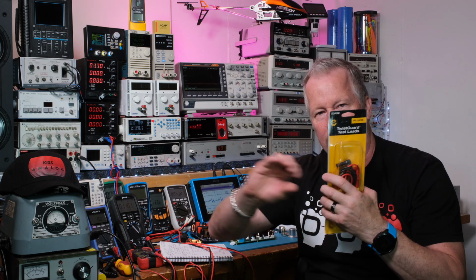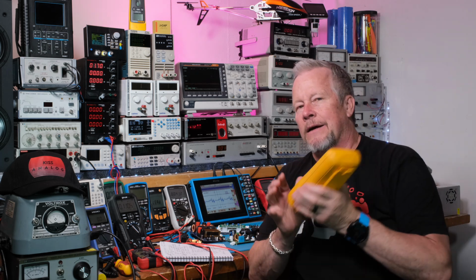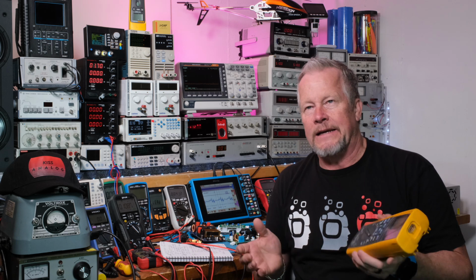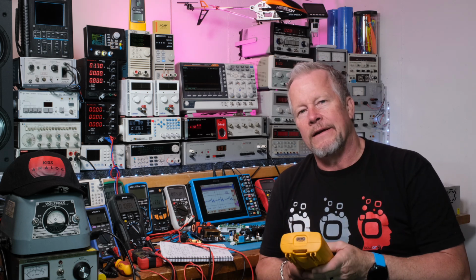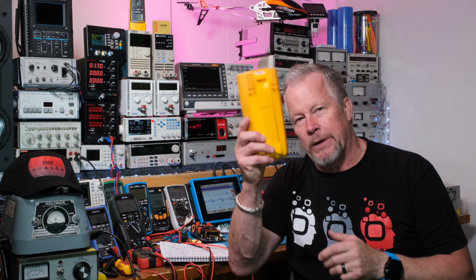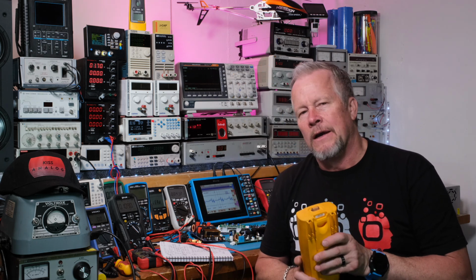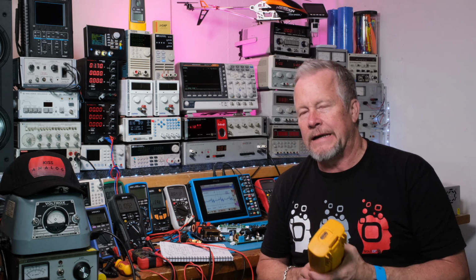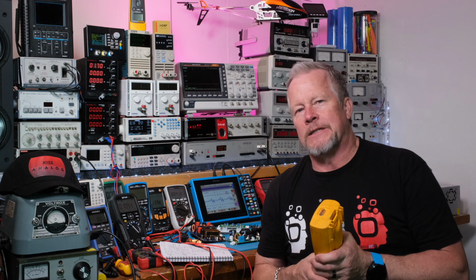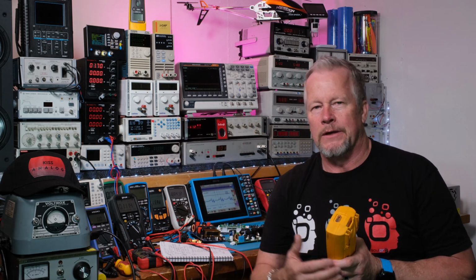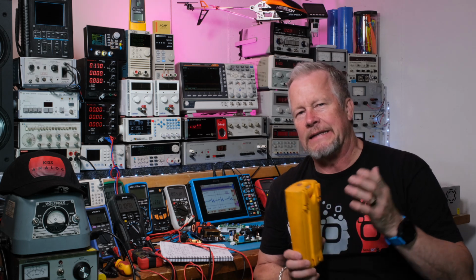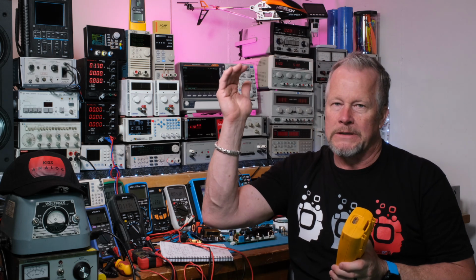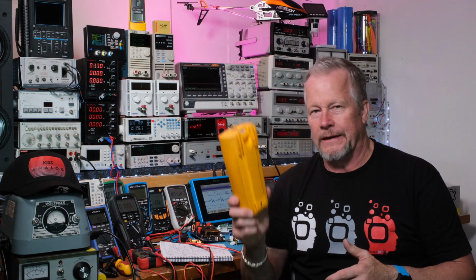These are Fluke's TwistGuard leads, the ones that rotate, and that Cat 4, Cat 3 cover comes down and protects it. By the way, I didn't mention that the Fluke 189, or down here the Fluke 289, and that Keysight meter, they are all Cat 4 meters, right? Cat 4 means the power outside the breaker box, coming to the residence or the building. That dangerous, scary stuff that has a lot of potential energy, more potential for surges and that kind of thing, where you need that protection.